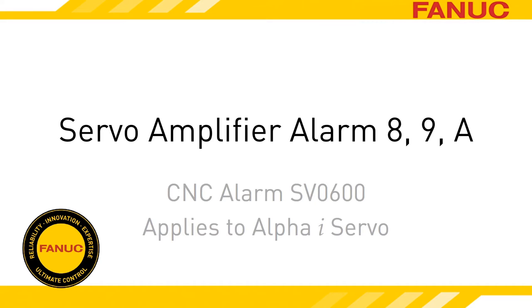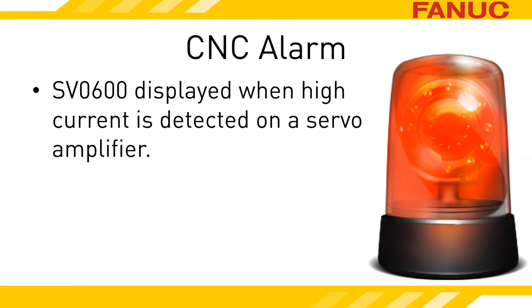Alarm 8, 9, or A on the Alpha-I Servo Amplifier is a High Current Alarm. Alarm SV0600 is generated by the CNC when it detects that an amplifier has a High Current Alarm.